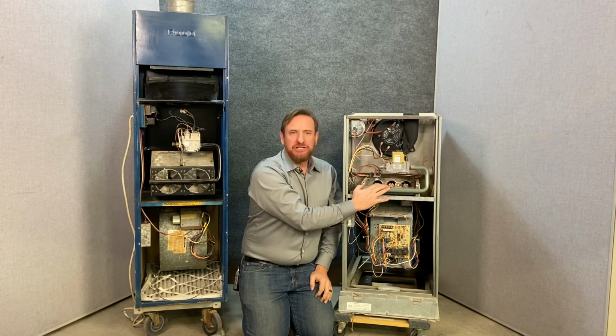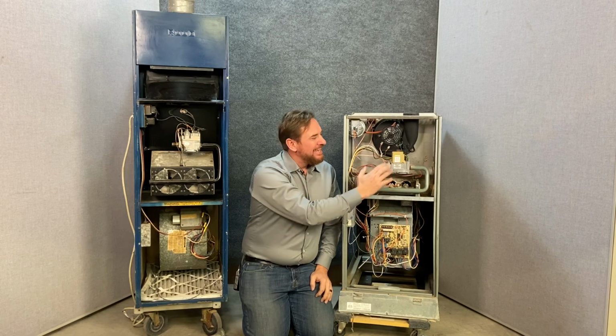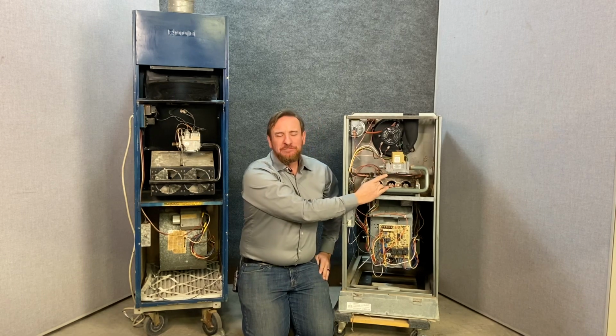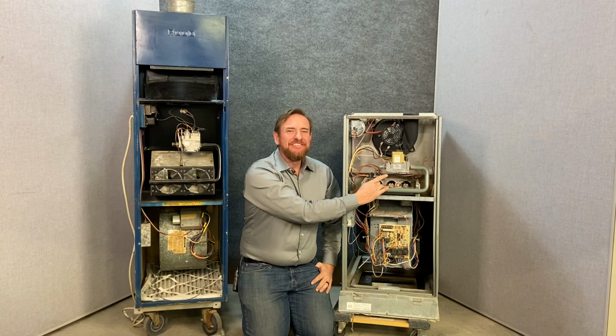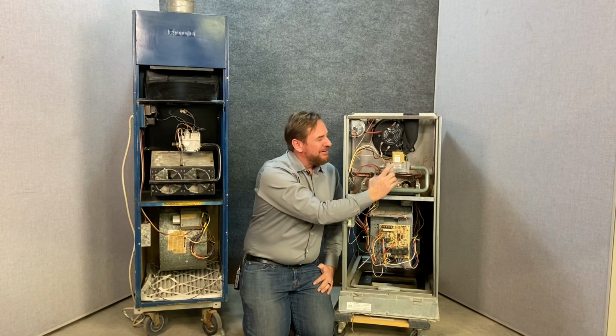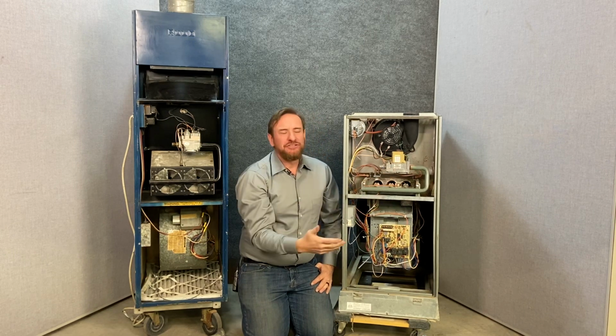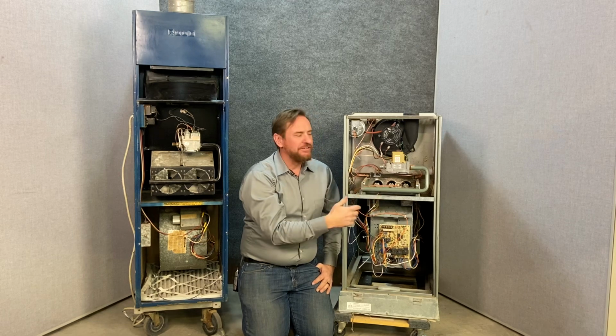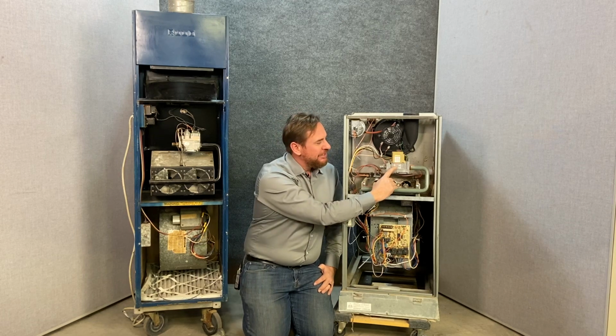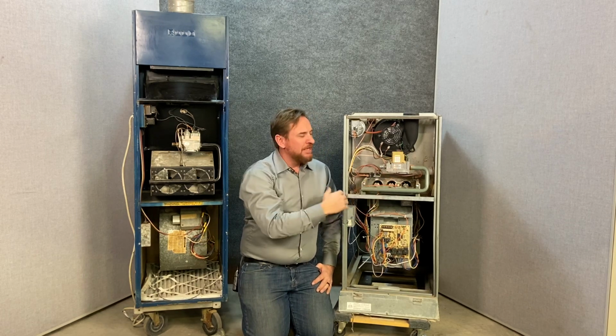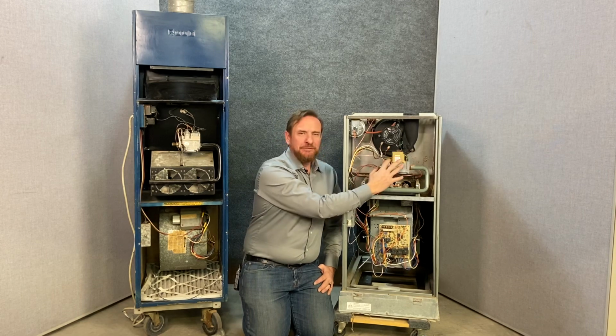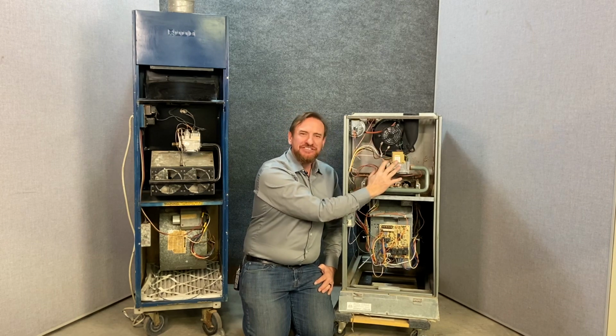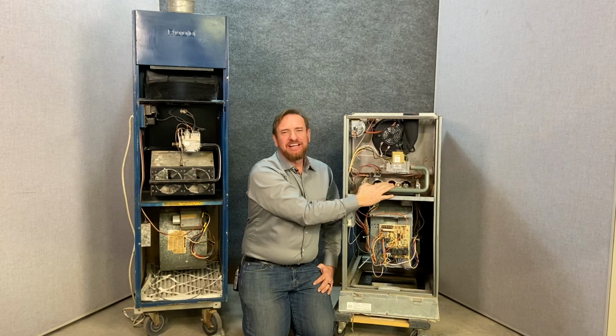However, it is important to make sure the gas pressure is set correctly. If you want to know the correct way to set the gas pressure, RTFM. Read the fabulous manual. Every system's a little different as far as altitude or changing spuds and orifices, but on most gas valves you'll see it says 3.5 inches of water column. So there are different settings for the gas pressure. Once you get the gas pressure set correctly, then the air side's already done for you.